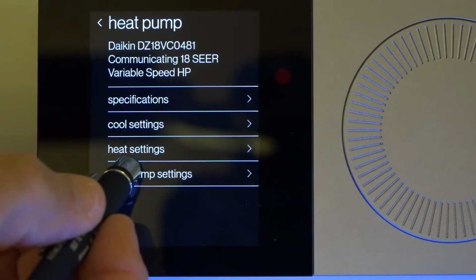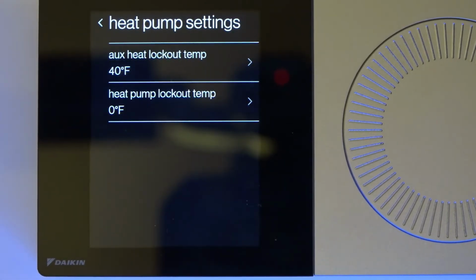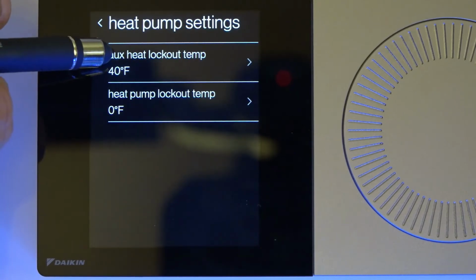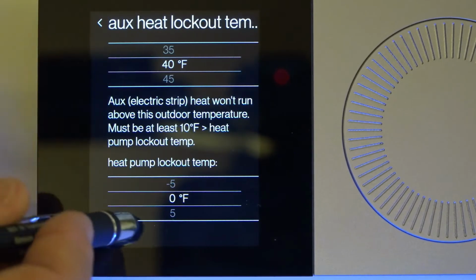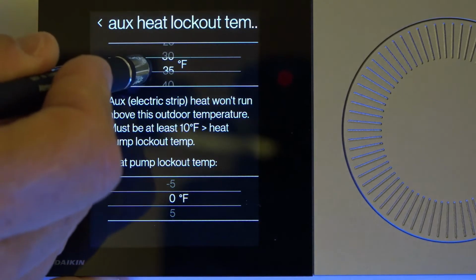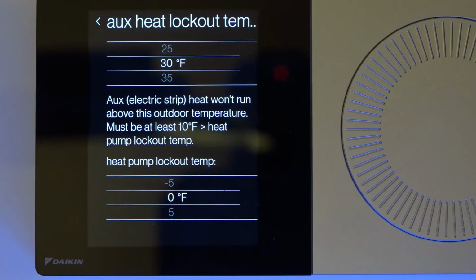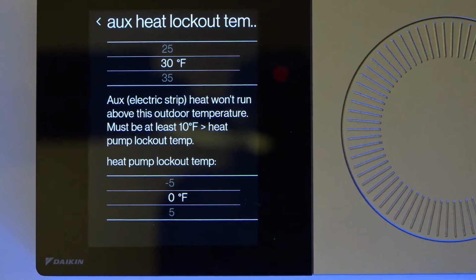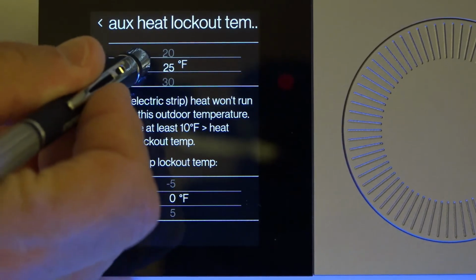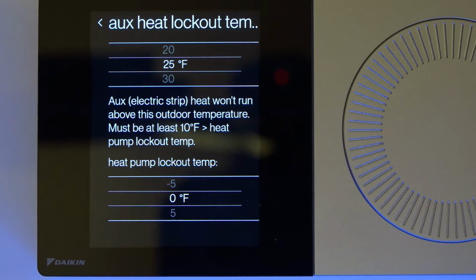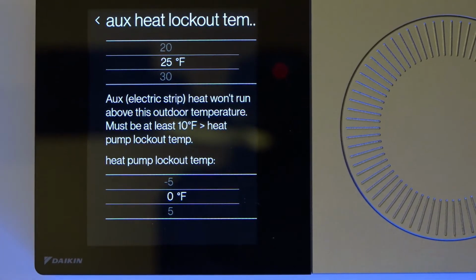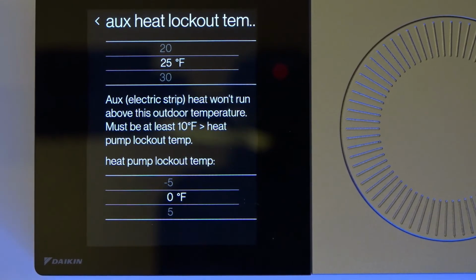Okay, under heat pump settings, I get a few other options. I've got auxiliary heater kit lockout. I can come in there and say never ever turn the electric heaters on above 30 degrees for supplemental heat, or I can drop it to 25 degrees. It's just really what my customer's needs are. Like again, if you've got someone on blood thinners, there are times where they need that extra heat to feel warm.